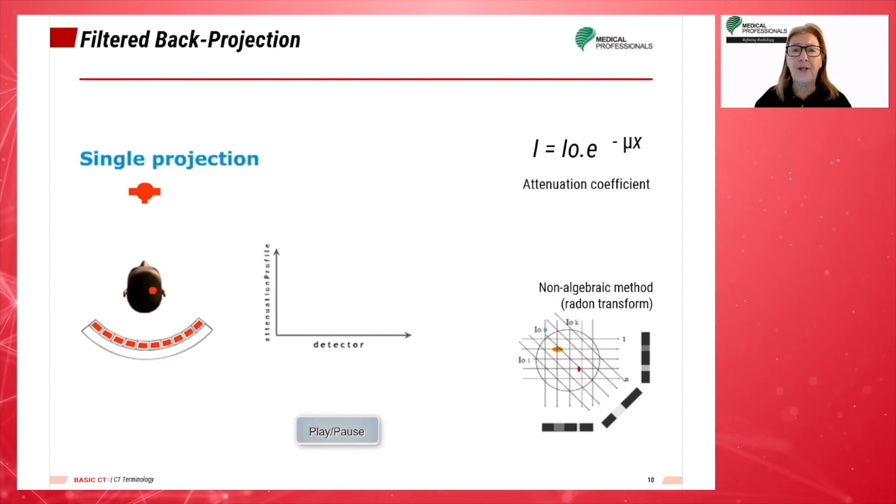Also known as filtered back projection, the projection profile is filtered or convolved to remove the typical blurring of the simple back projection technique. Applying a filter function to an attenuation profile is called convolution. Filter functions may be referred to as algorithms, convolution filters, or kernels. Filter functions can only be applied to raw data.